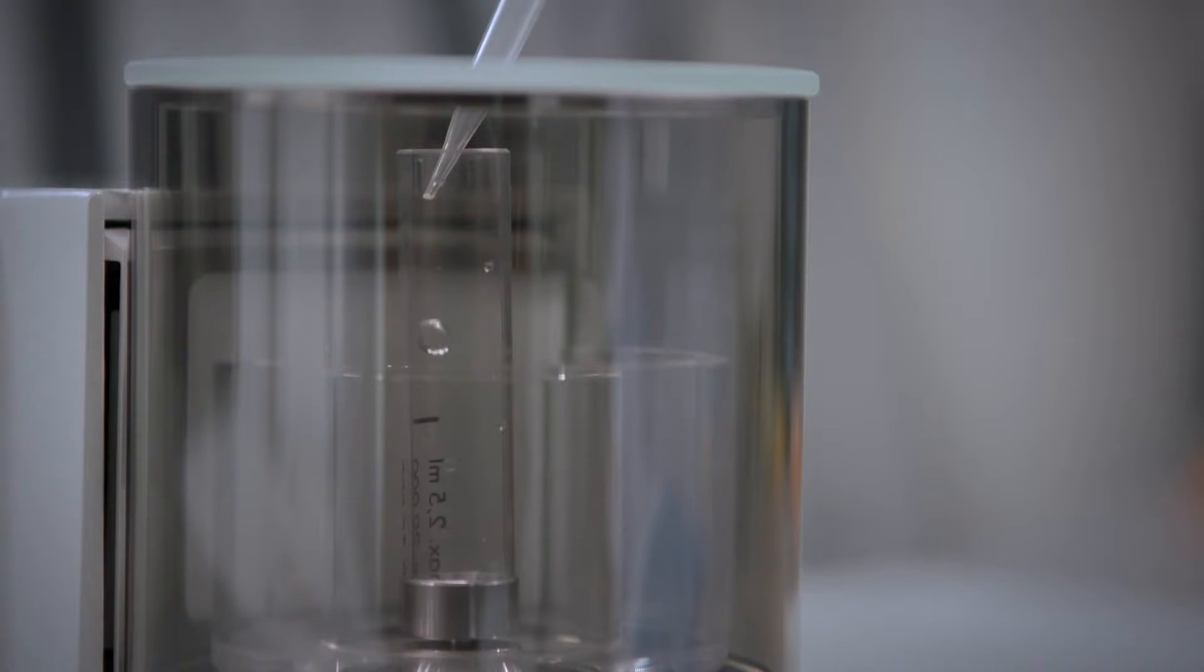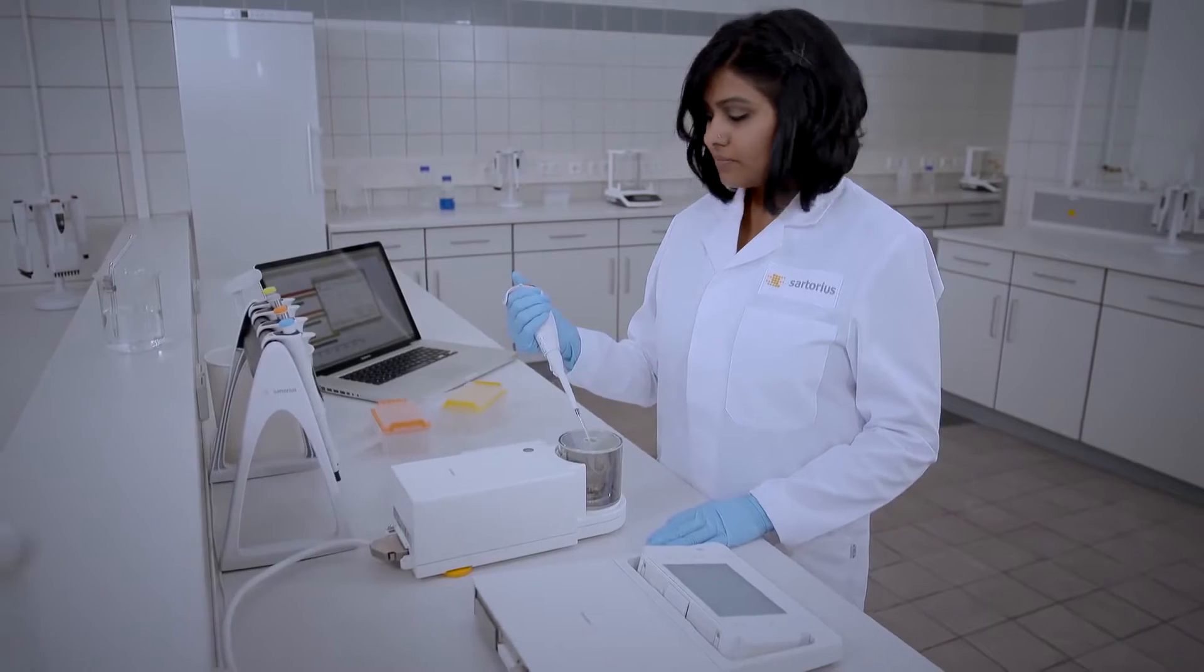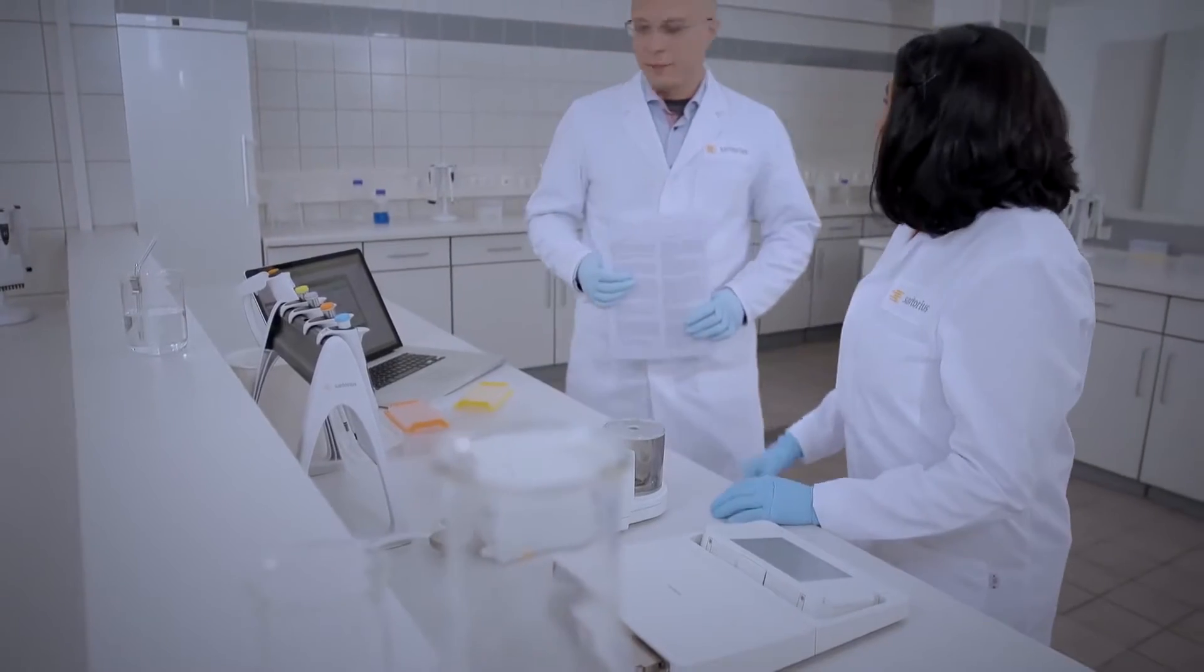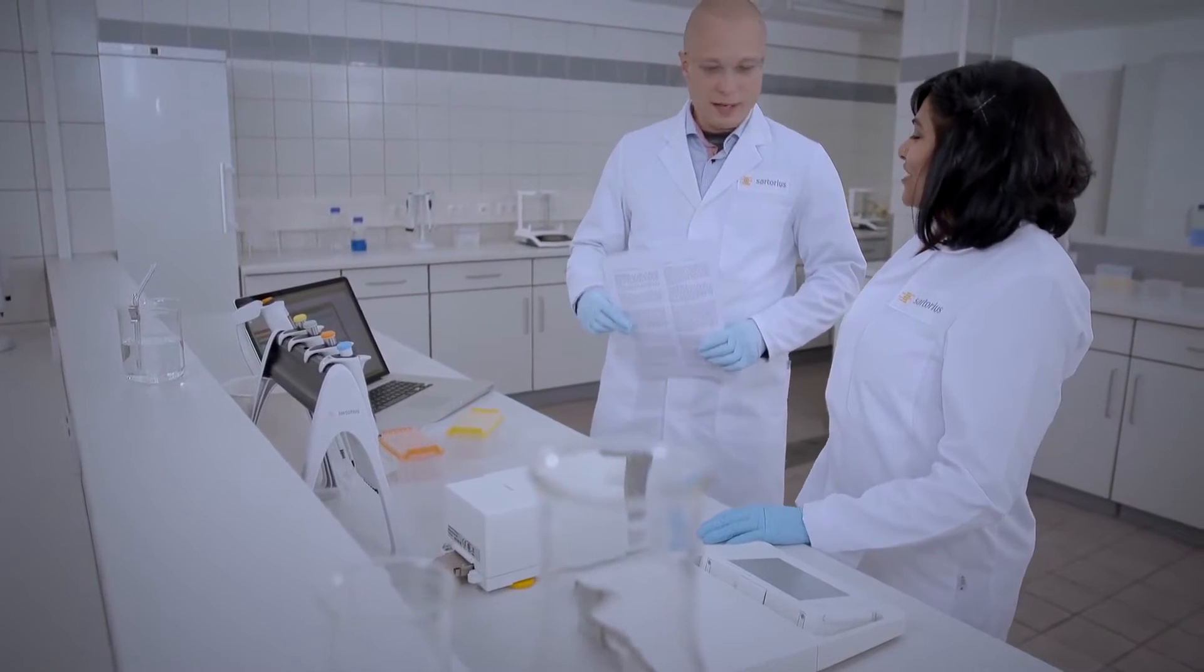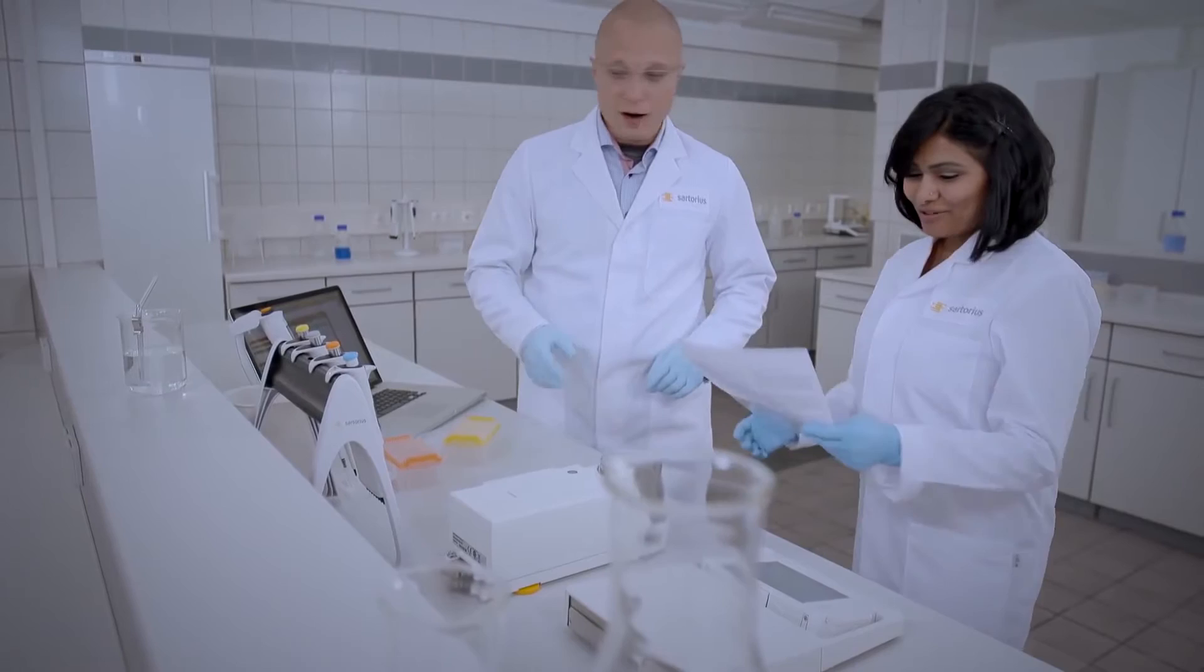A calibration certificate is as important as the calibration procedure itself. It documents your results as well as the equipment and people involved in the process. An accredited certificate will also show the uncertainty of measurement for your instrument.